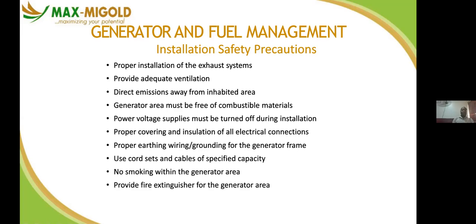These are the safety precautions that you must take when you are installing your generator or equipment. Proper installation of the exhaust system. The exhaust should not be where it can disturb other users of your building or facility. Provide adequate ventilation, because if there is no adequate ventilation, your generator will overheat. Before you know it, it will knock, it will burn your top gasket and eventually your generator will knock. Ensure that the radiator is working the way it's supposed to work. It's not close to the wall. There should be a gap.